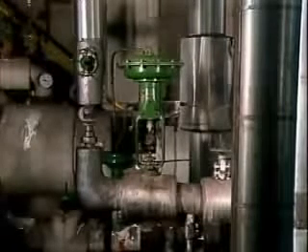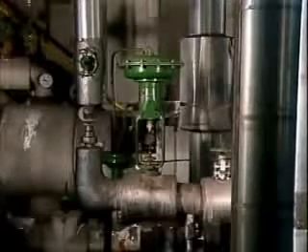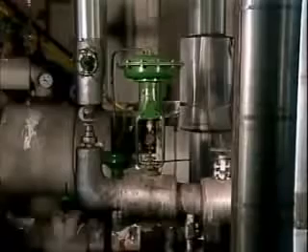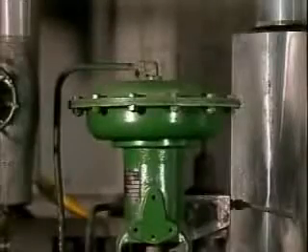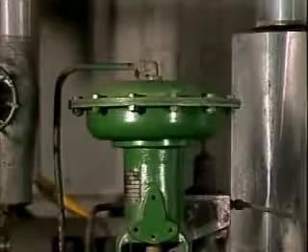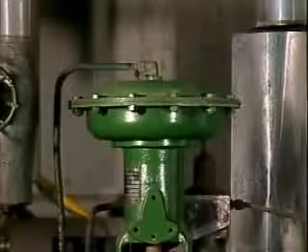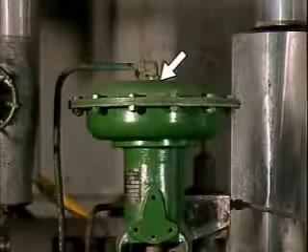Types of pneumatic actuators is the diaphragm actuator. In a diaphragm actuator, air pressure acts on a flexible diaphragm to position a valve.